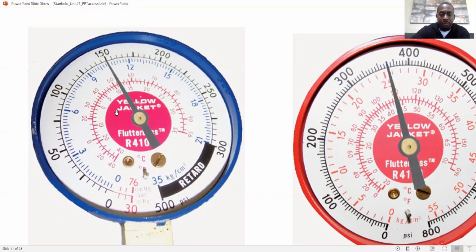The drawback for the mechanical gauges is that this particular one only has one scale for 410A refrigerant. So if you were on a system that was using R22 or 134A or something like that, then this scale would not tell you the correct saturation temperatures. At that point, you would have to pull out a pressure temperature chart and compare that pressure to the corresponding temperature for your given refrigerant on that chart.